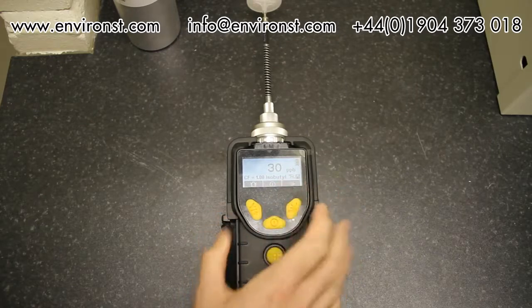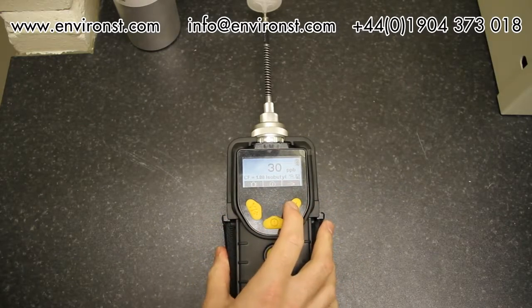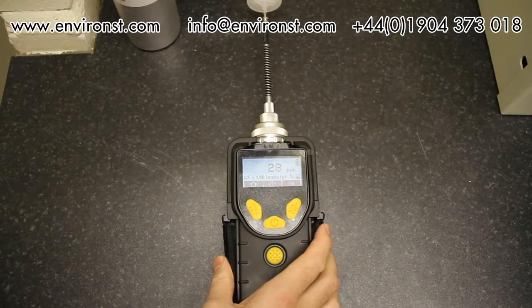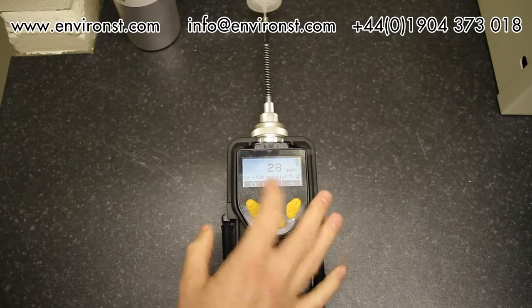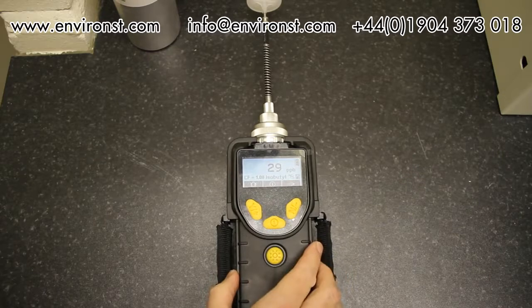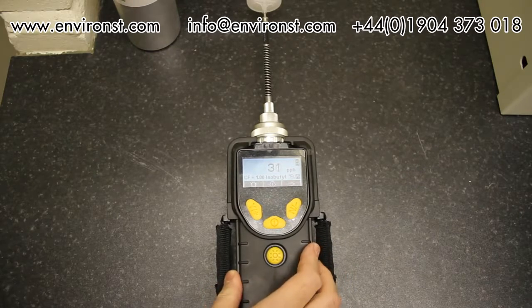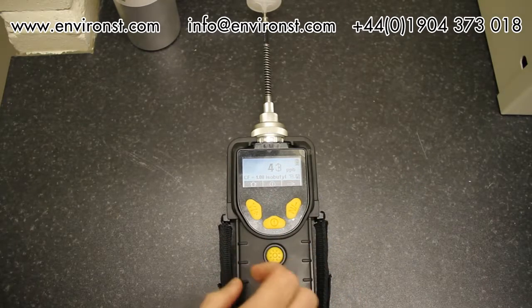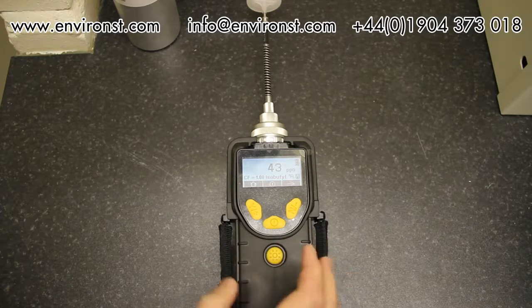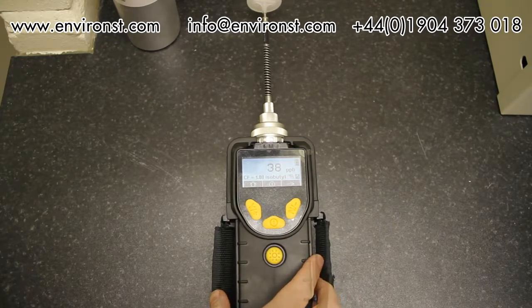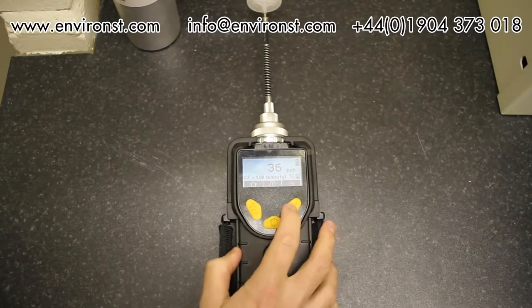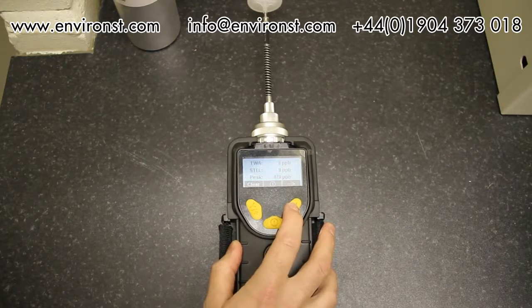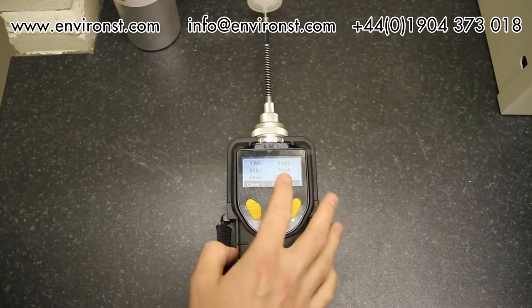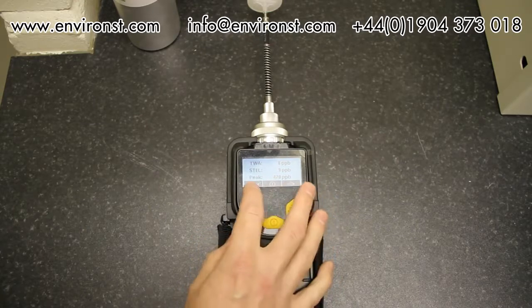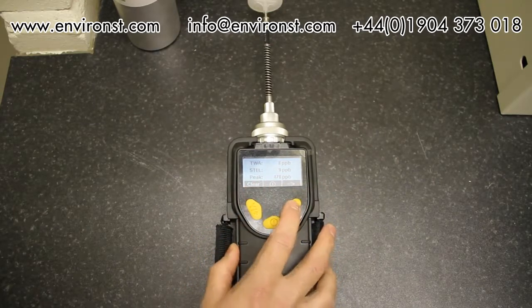Now you can see we've got 30 parts per billion of ambient VOCs. Now we're indoors, so you'd expect to see some sort of VOC knocking around. This is a particularly low reading. Normally indoors, if you're in a proper indoor environment, lots of office furniture, that sort of thing, you'd expect to see in the region of about 300 parts per billion. So if we quickly scroll through the screens here, we've got 34 ppb-ish on screen at the moment, and we've currently got a TWA of 8 ppb, a STEL of 9 ppb, and a peak of 470 ppb.